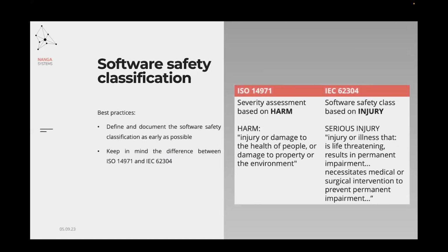It is best to define and document the software safety classification as early as possible. Identifying a higher class late in the development process might lead to increased costs and additional work to comply with newly introduced requirements in the development process. These requirements are indicated in IEC 62304, as I mentioned. So it is quite important for us to define the appropriate safety class as soon as possible.